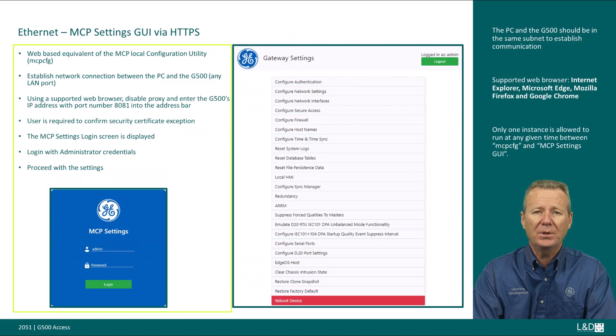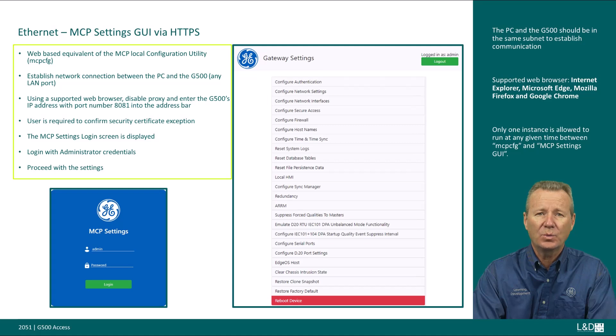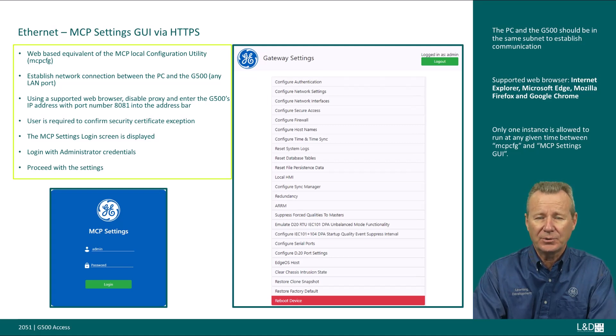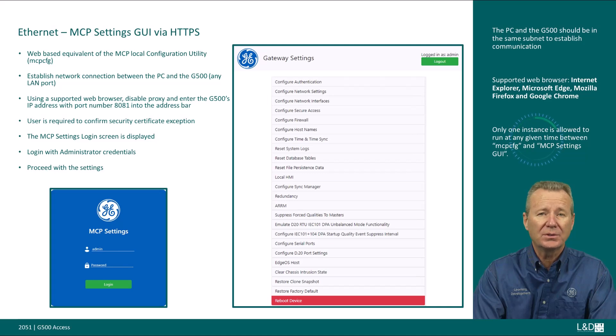The MCP settings GUI can be launched remotely via HTTPS. The PC and the G500 shall be in the same subnet to establish a network connection. Use a supported web browser such as Internet Explorer, Microsoft Edge, Mozilla Firefox, or Google Chrome. Disable proxy and enter the G500's IP address with port number 8081 into the address bar. The user is required to confirm the security certificate exception. The MCP settings login screen is then displayed. Log in using administrator credentials. Only one instance is allowed to run at any given time between MCP CFG and the MCP settings GUI.